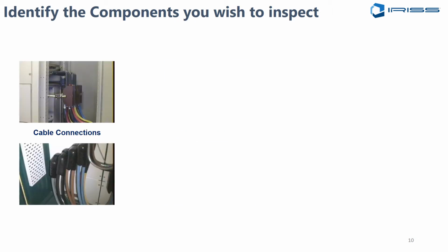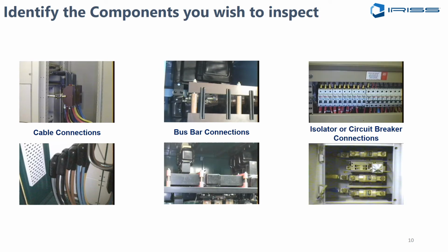So in electrical systems, they're typically cable connections, bus bar connections, and isolator or circuit breaker connections. Other than through human intervention, I don't really see bus bars failing or cables failing outside of their joints or connections, and that's a broad spectrum thing. There are systems that do fail like that, but again, these are typically where we're looking at cable connections, bus bar connections, and the isolator and circuit breaker connections, the mechanical parts of the system.